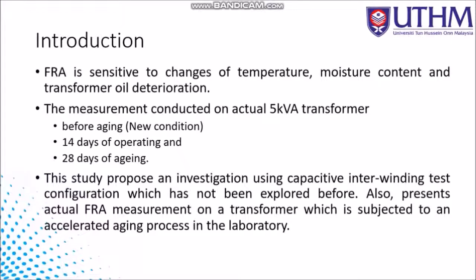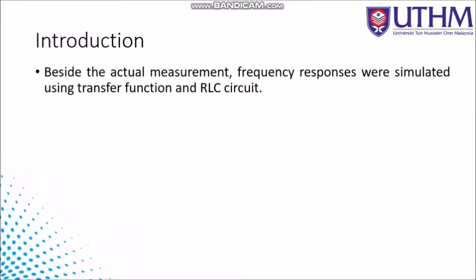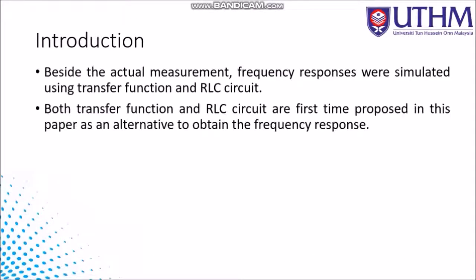This study proposes an investigation using the capacitive interwinding test configuration, which has not been explored before. It also presents an actual FRA measurement on a transformer subjected to an accelerated aging process in a laboratory. Additionally, actual measurement frequency response was simulated using a transfer function and an RLC circuit — both first proposed in this paper as an alternative to obtain the frequency response.